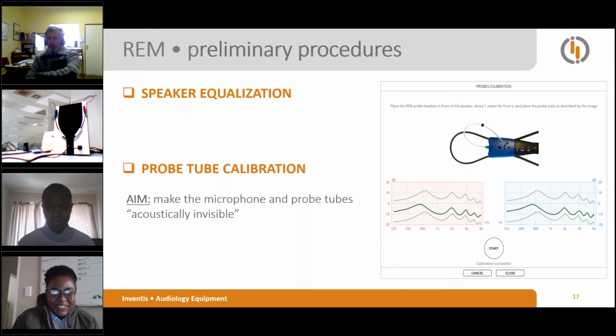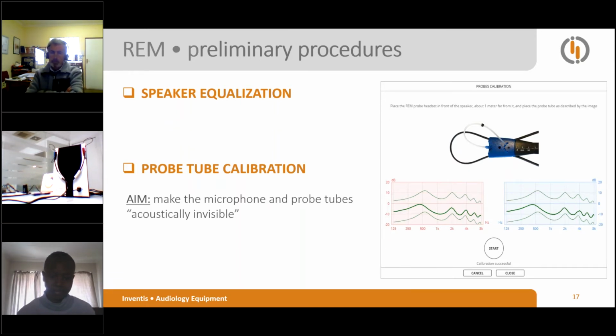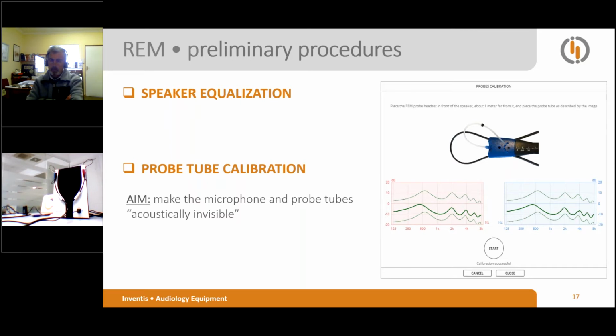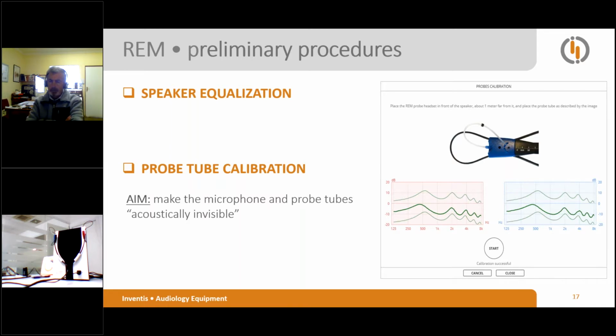Okay. So the second operation, as I said, is the probe tube calibration. Let me repeat this relevant passage. The probe tube's calibration takes into account the acoustic effects introduced by the tubes used during the examination. Therefore, in order to make the microphone and the tube probe acoustically invisible, this type of calibration is necessary. The figure you should see on my screen shows how to position the probe tube in order to proceed with the calibration. The probe tube tip must be placed as close as possible to the reference microphone of the probe headset. It is very important.